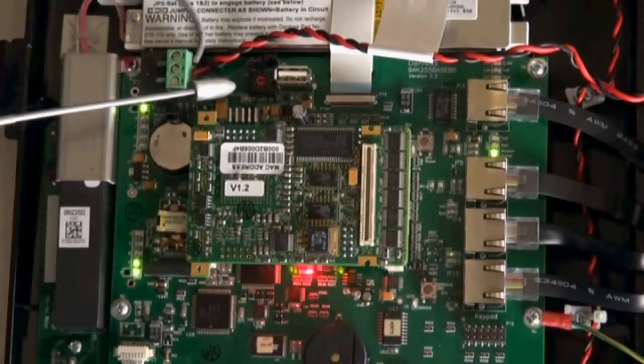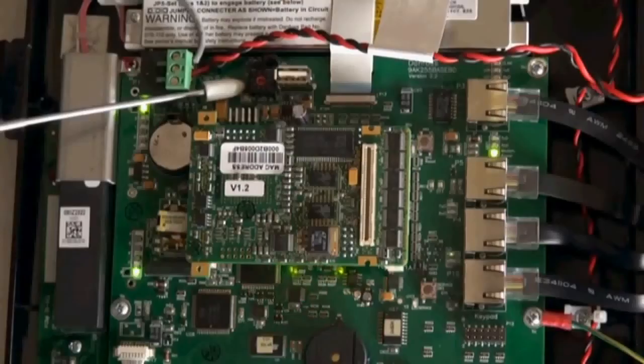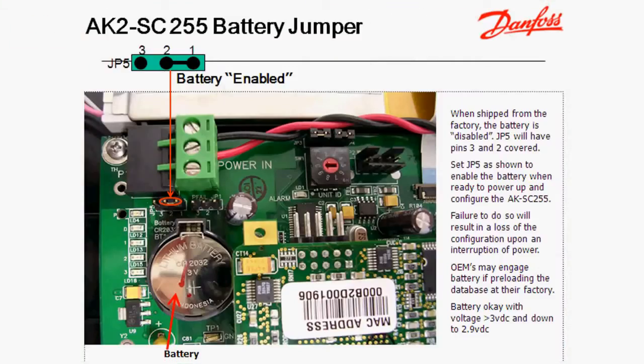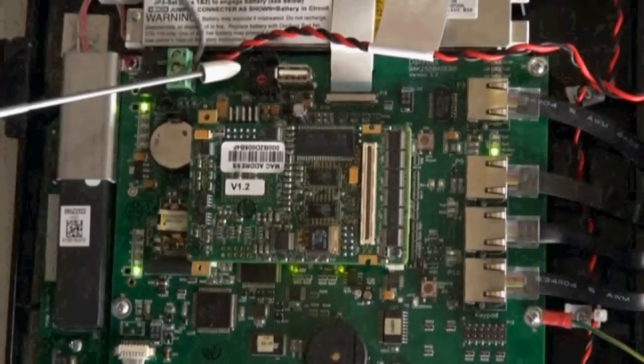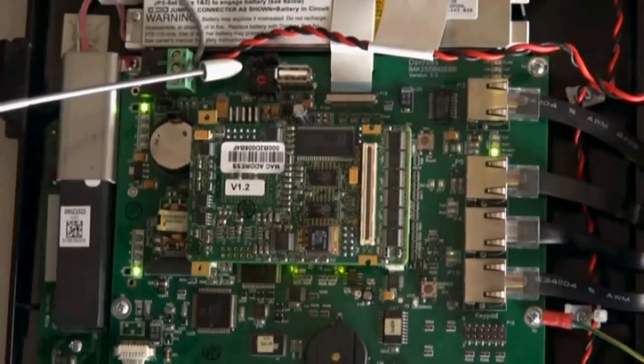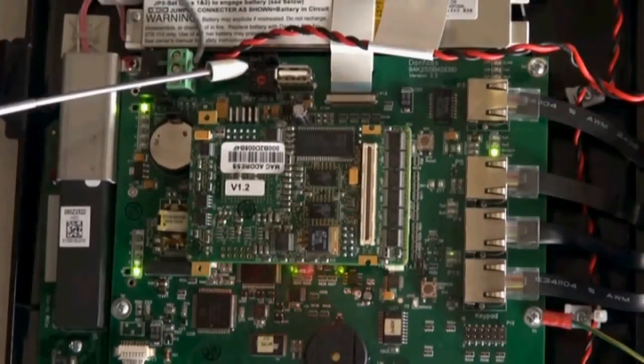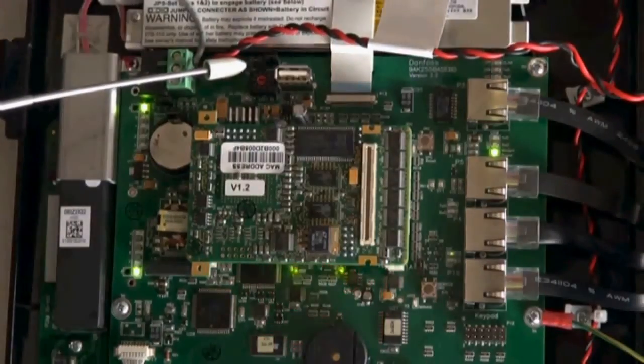Next we'll look at the rotary address switch, which is used to give the 255 its number. Addresses always start at 0 and can go as high as 9. Here we find the RS-485 function jumpers. These would get removed under normal situations unless you're using Modbus RS-485 I/O nodes.